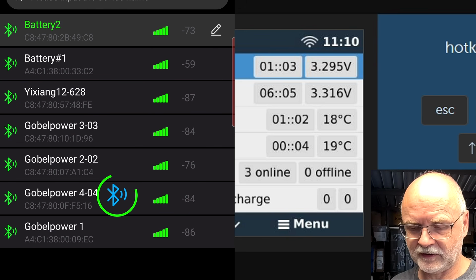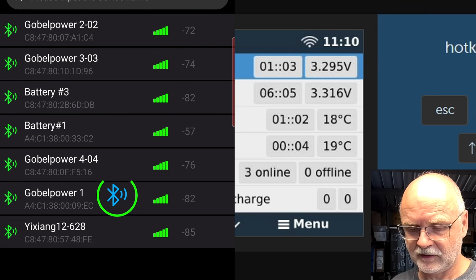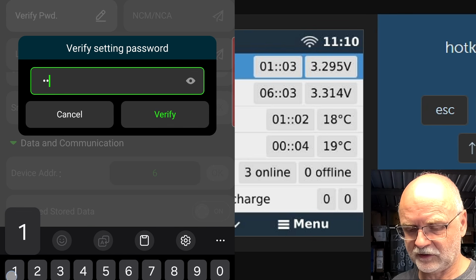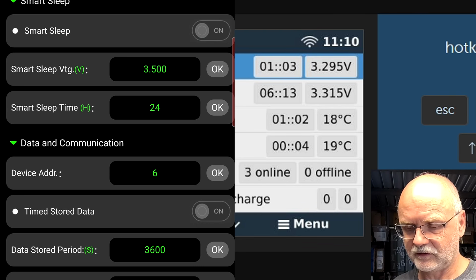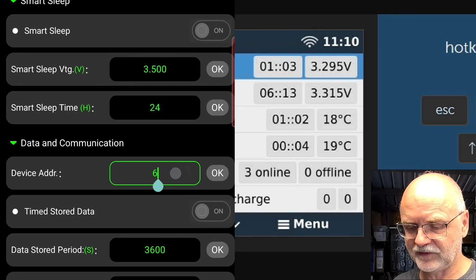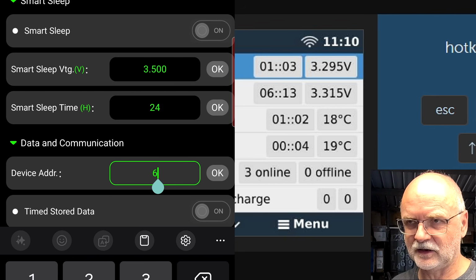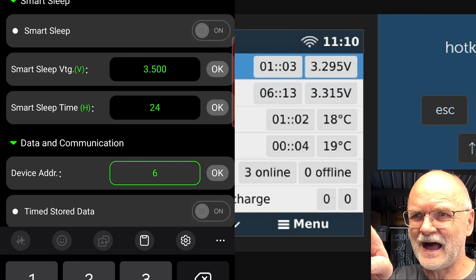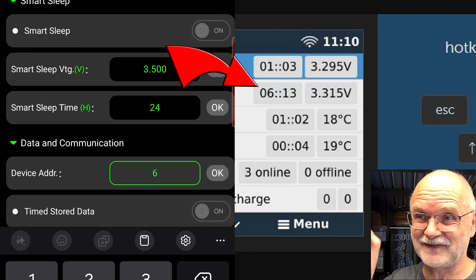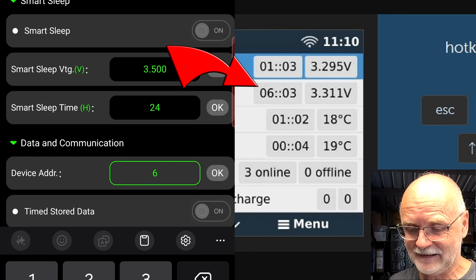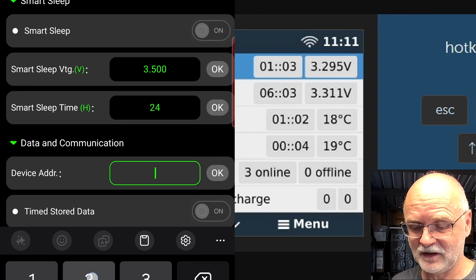And battery number 3, there it is, that's the bottom shelf battery. Password, 1, 2, 3, 4, 5, 6. Address number 6 - shouldn't make a difference. Yeah, we can see it already here, highest cell voltage is in battery number 6, which is our bottom shelf battery. But for the sake of keeping things in order, let's set this one to device address number 2, yeah.